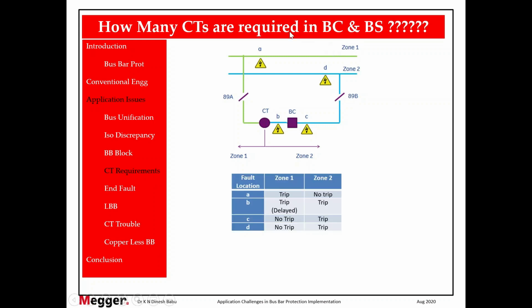Let us understand. Fault at location A: zone 1 will trip, zone 2 will not trip. Perfect. Fault at location B: zone 2 will trip, zone 1 will also trip, but there is a delayed tripping. Now what is this logic? Why are we calling it a delayed trip?